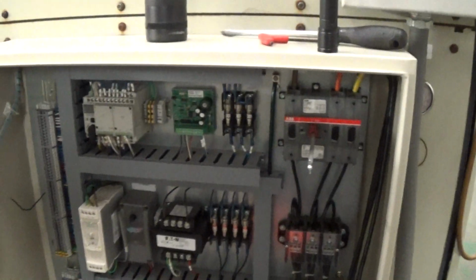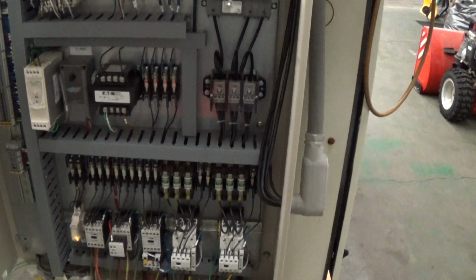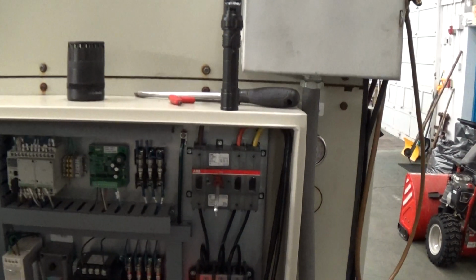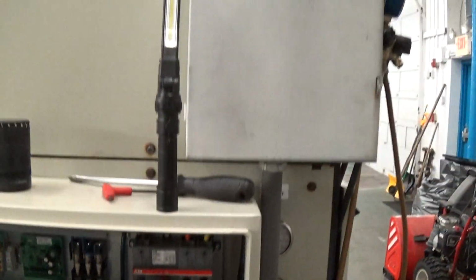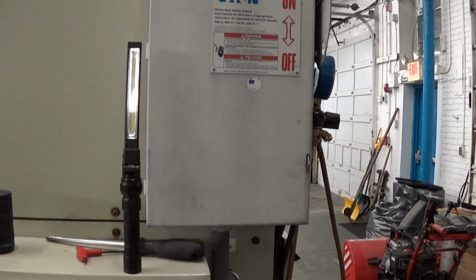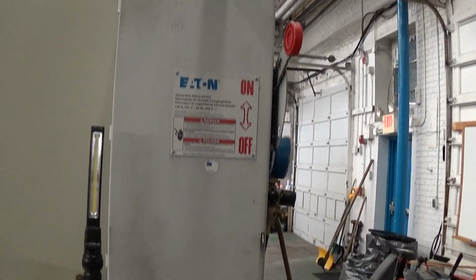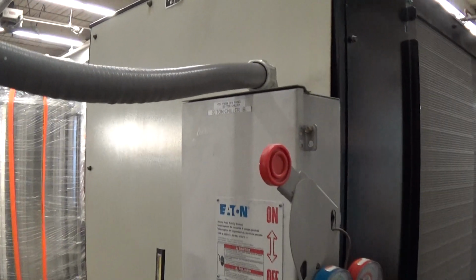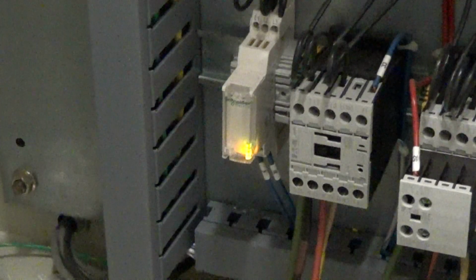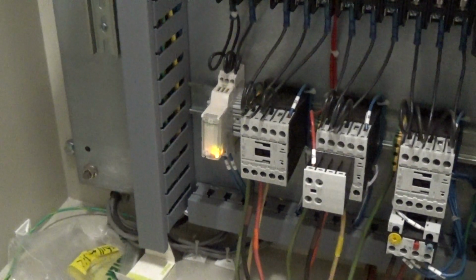This is the inside of our electrical area. It's essentially going to be pre-wired in here, because we're going to ship it with the disconnect, which it came with. It has a couple of 300 amp fuses in there. So the customer's going to bring their power into the top of the disconnect here. The unit does have a phase monitor, which is nice. So right down here, kind of tough to see with the camera. They both look yellow. But if a green light comes on, your phase is good. If it doesn't come on, switch any 2 out of the 3 hot legs going into your disconnect.